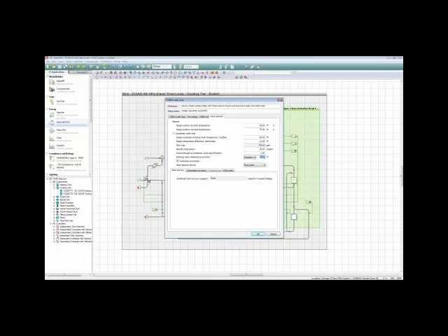It means that this is going to try to maintain a 70-degree water temperature entering the condenser tube bundle whenever it can. And when it's unable to do that because of outdoor conditions or loads or both, then this condenser water temperature is going to rise up towards the design value. And if this is properly sized, it should not ever exceed that design value.